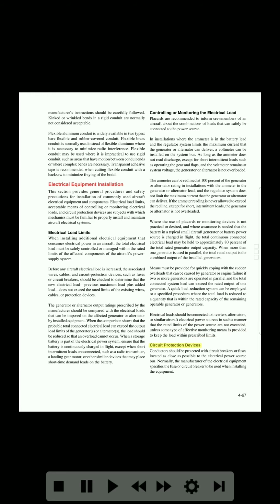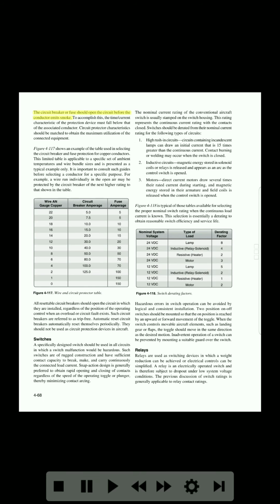Circuit protection devices. Conductors should be protected with circuit breakers or fuses located as close as possible to the electrical power source bus. Normally, the manufacturer of the electrical equipment specifies the fuse or circuit breaker to be used when installing the equipment. 4-67. The circuit breaker or fuse should open the circuit before the conductor emits smoke. To accomplish this, the time/current characteristic of the protection device must fall below that of the associated conductor. Circuit protector characteristics should be matched to obtain the maximum utilization of the connected equipment.